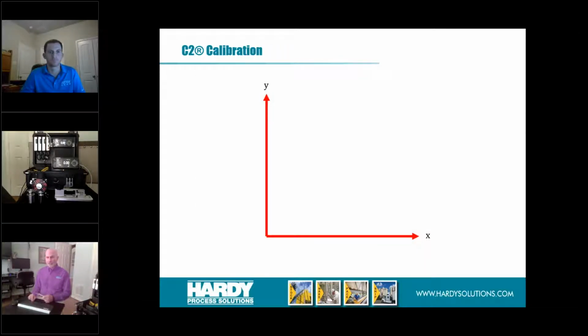So for traditional calibration, we'll start with the XY axis - we're going to put volts on the Y axis and weight on the X axis. We'll have a 0 point, and we'll say that full scale for this scale, on the electrical side, full scale is 10 millivolts, and on the weight side, it's 10,000 pounds. We just pick these numbers to make the math easy whenever you have 10 and 10 like that.